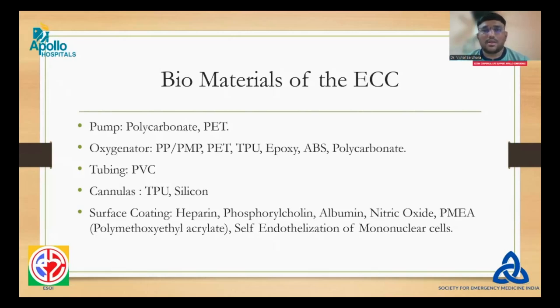They are biocompatible, but still there are some surface reactions which happen. Also, the tubing which is being used is DEHP-free polyvinyl chloride (PVC) tubing of various sizes like 3/8, 1/4, 1/2, and 1/16 as per the requirement of the flows.